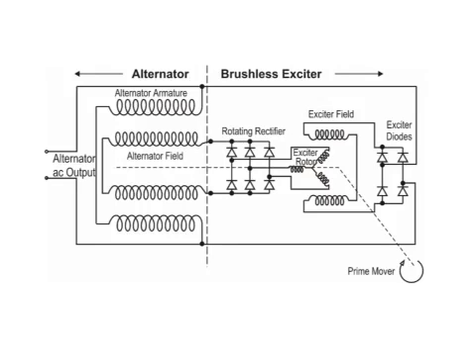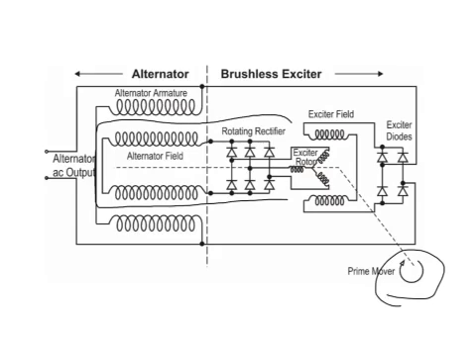Let's look at what happens when we start making this thing turn. Your prime mover is turning the entire rotor portion, and your rotor consists of your alternator field along with your rotating rectifier, and that also includes the exciter rotor — which is the armature of your exciter. That whole rotor assembly turns via wind, water, nuclear, or whatever prime mover you have. Keep that in mind as we go through this.